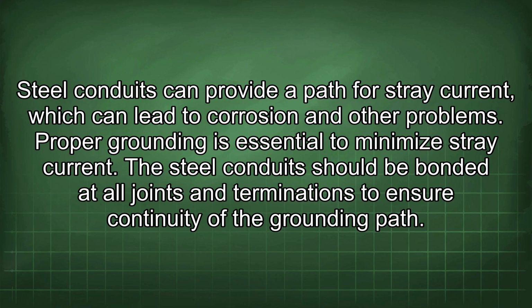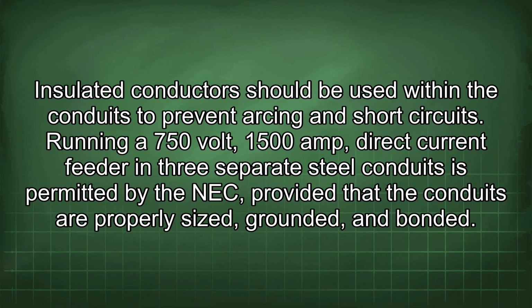Proper grounding is essential to minimize stray current. The steel conduit should be bonded at all joints and terminations to ensure continuity of the grounding path. Insulated conductors should be used within the conduits to prevent arcing and short circuits.